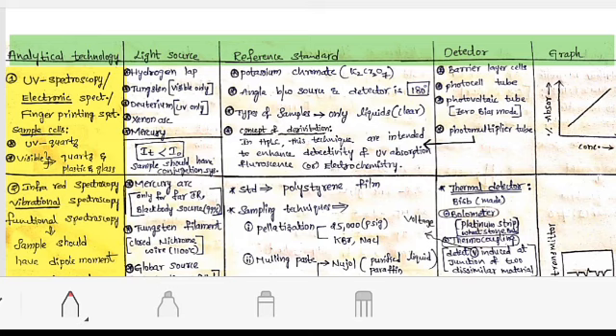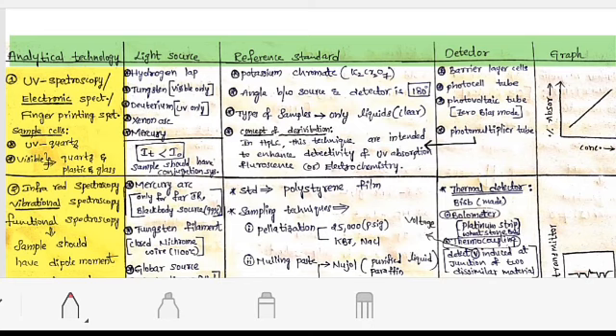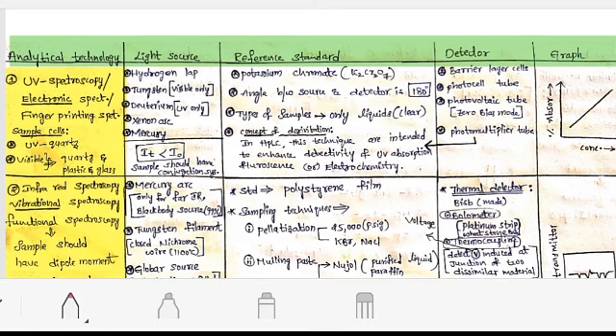Reference standard in UV spectroscopy is potassium dichromate K2Cr2O7. The angle between the source and detector is 180 degrees, meaning you have to keep the detector and source in a straight line. The type of samples used should be only liquid and that liquid should be clear.